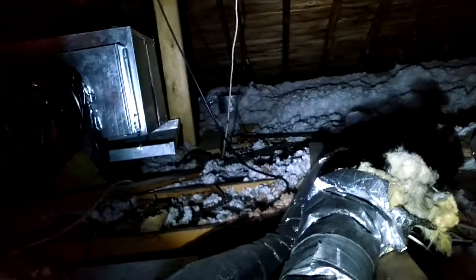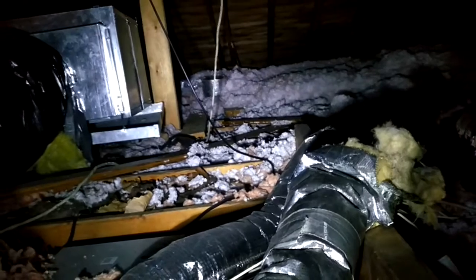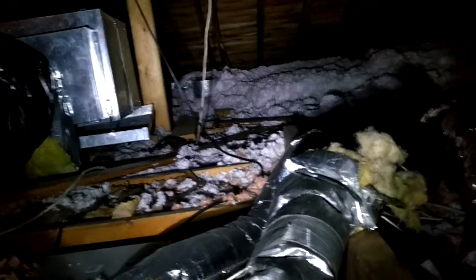The unit itself is not level — it's hard to see at this angle. Also, that drain pan, they just made it from sheet metal. I don't know if you can see the screws at the side of it, but that thing is not gonna do anything if the drain hose or coil freezes up or anything like that — it's gonna leak. It's garbage.